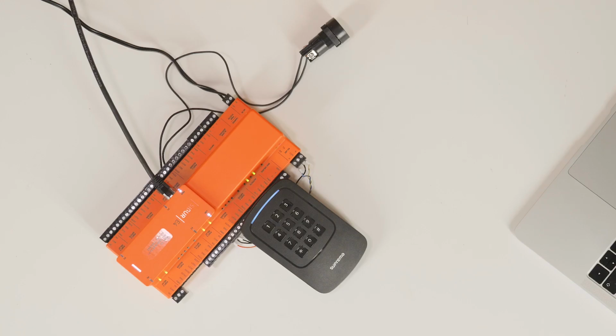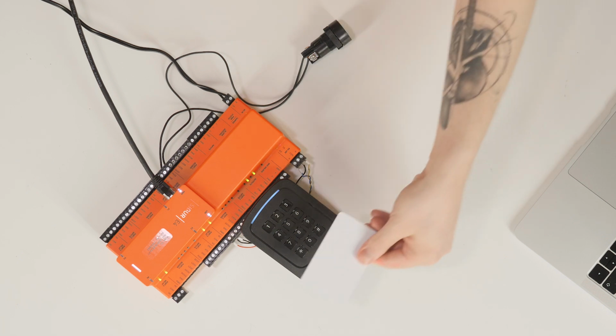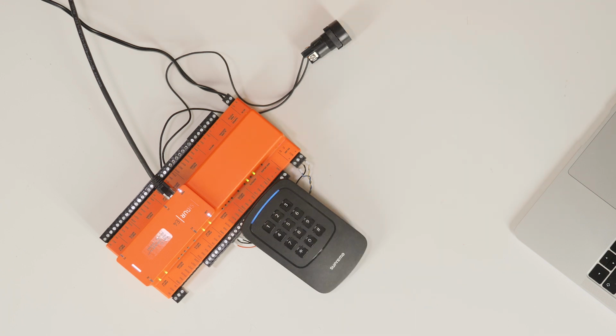Let's test its operation. Let's present an authorized card to the reader. The device successfully read the identifier and reproduced the configured light and sound indication of access permission. Now let's present the unauthorized card. The device reproduced the configured access denial indication. Let's simulate a door held open event. The device consistently shows the configured indication as per the software settings for the duration that the event remains relevant and applicable. Now, we will switch the access point to the unlocked state and then to the locked mode as per the required configuration. We see the signal at the reader showing the status of the access point.